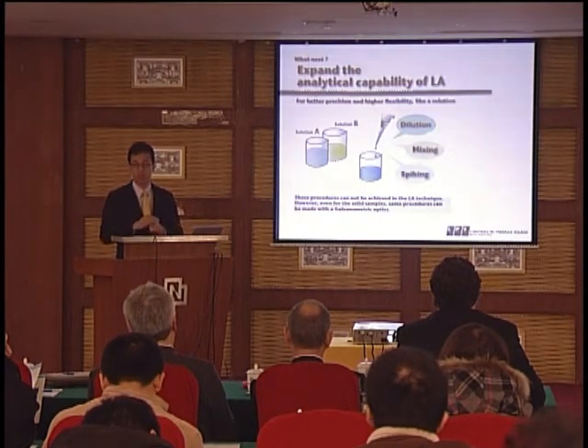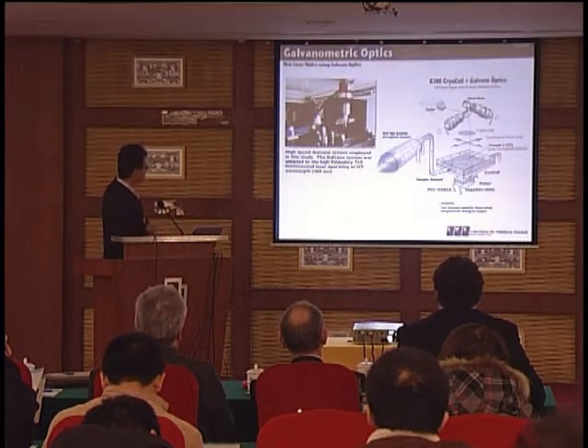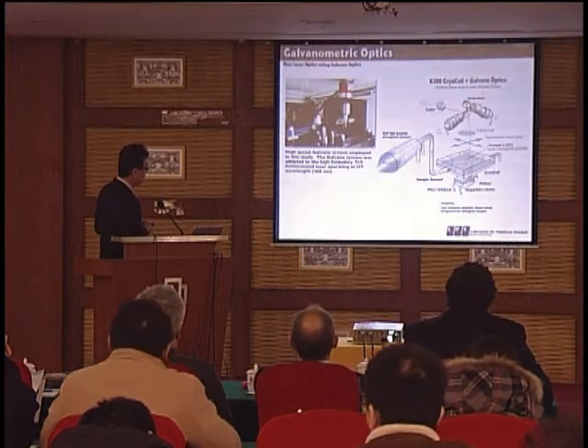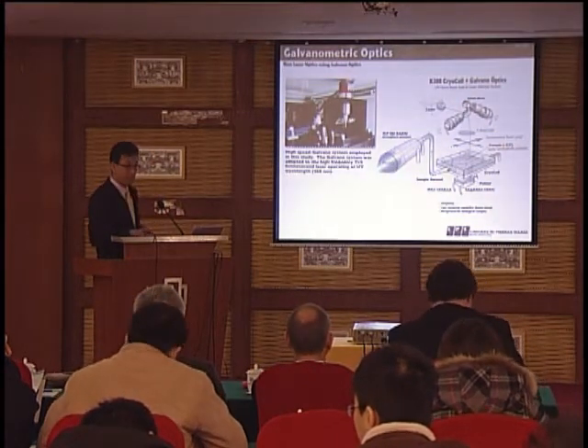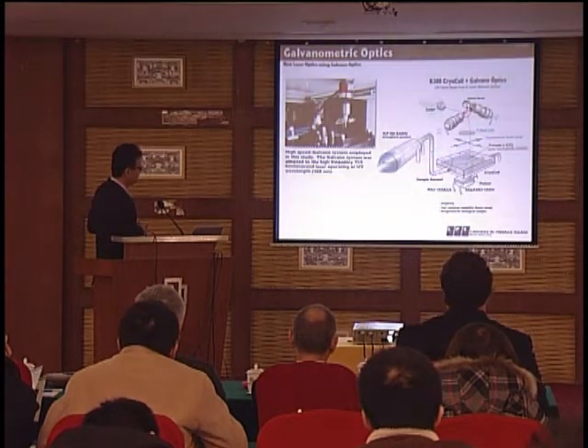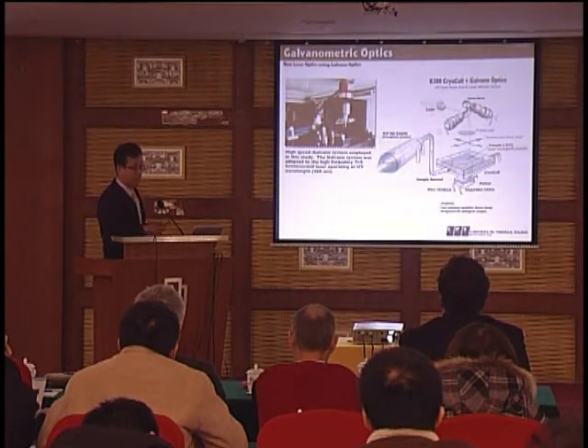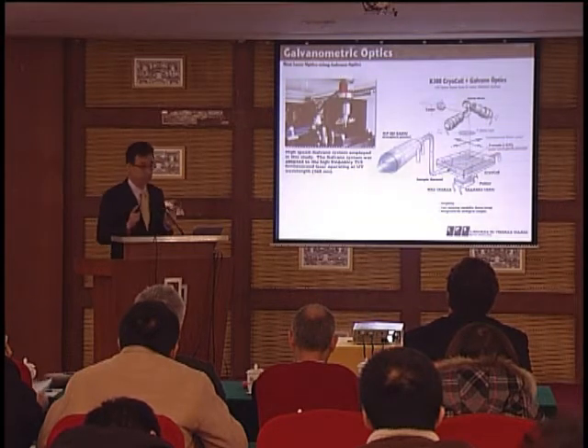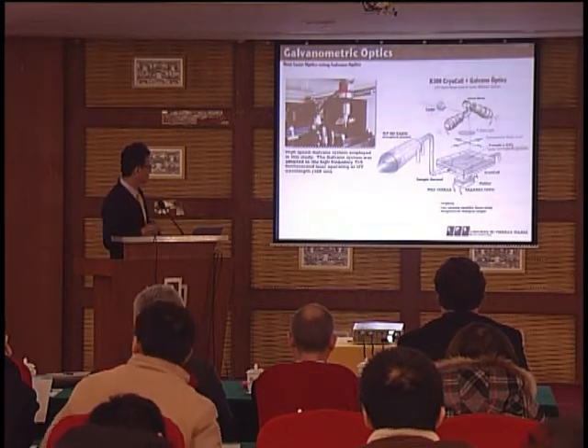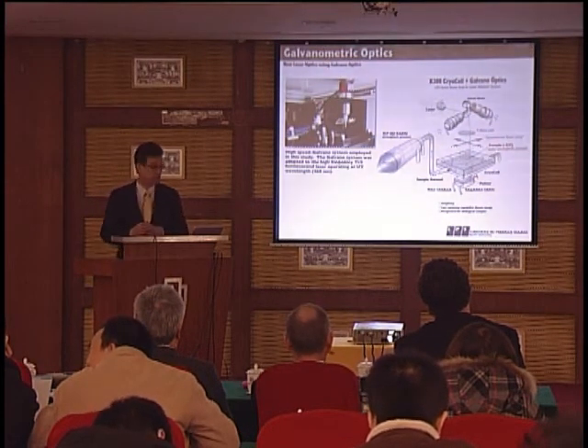Galvanometric optics is very important. It is quite simple — composed of two rotation mirrors. This mirror is rotating very precisely, so we can change the ablation pit at very high speed. The time required for changing the ablation pit is faster than 10 milliseconds. So we can switch the ablation pit quite fast, enabling so many operation modes using galvanometric optics.